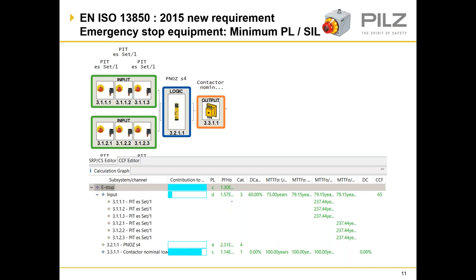It must be mentioned that performance level C is a minimum requirement, and a higher performance level such as performance level D or E could be required. If this is the case, you should consider your design and whether other protective measures in addition to e-stops are required. E-stops are a complementary device and are usually actuated following the occurrence of a hazardous event — an e-stop is an after-the-event safety device.